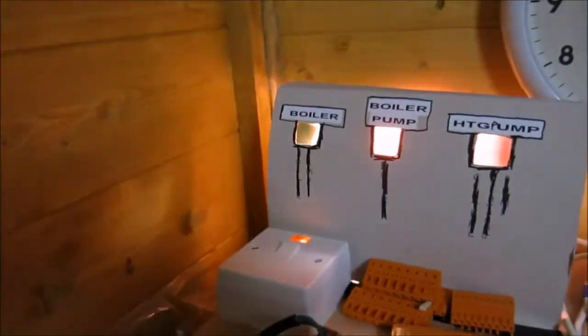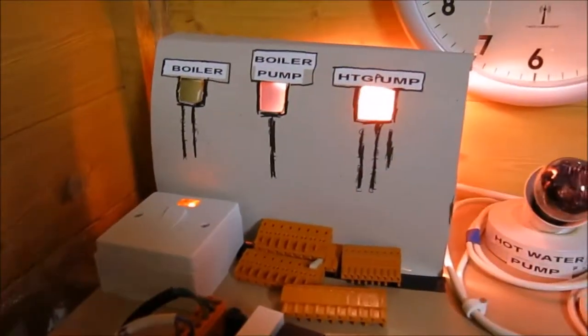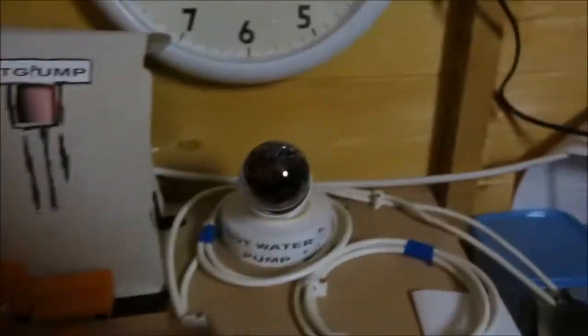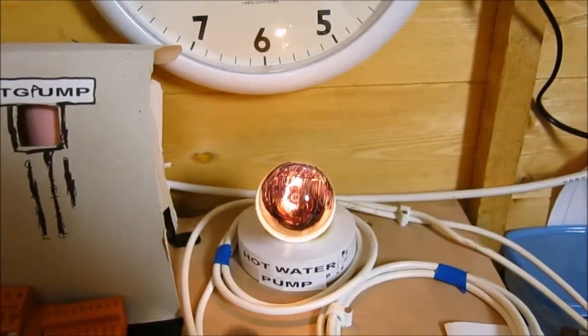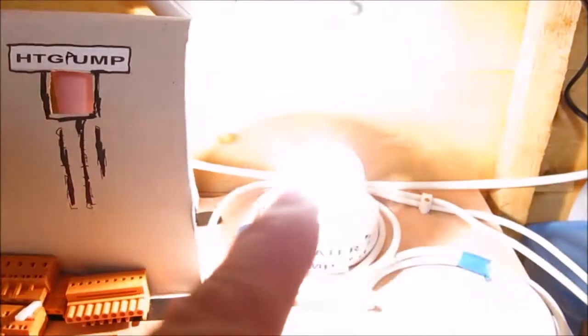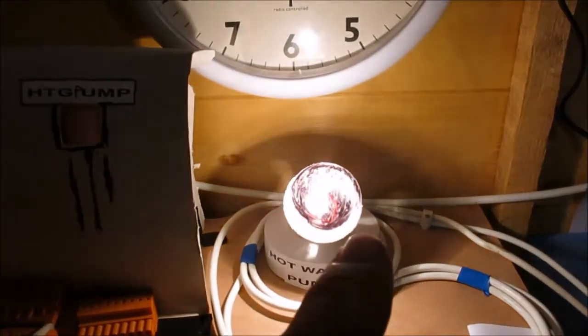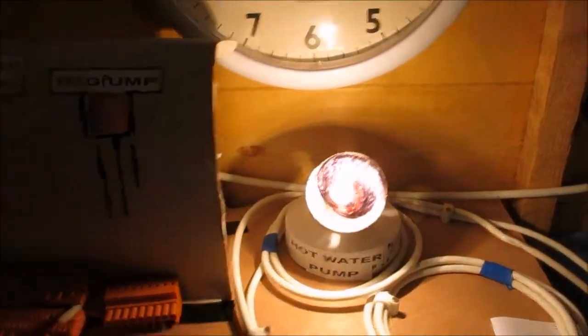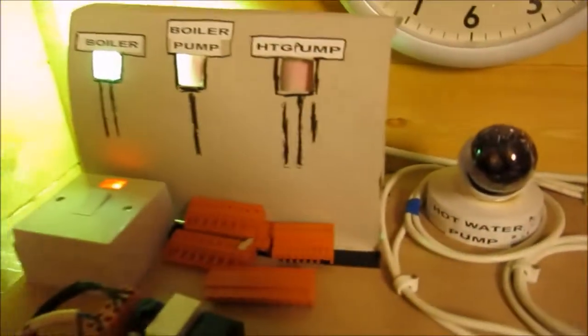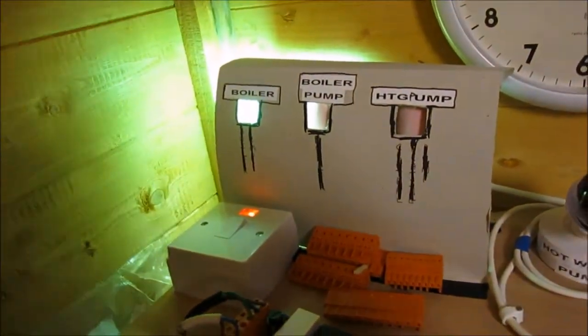So it'll run the boiler pump, the boiler, then the boiler pump, then the central heating pump. Then there's nothing on the next output. Then the direct hot water pump on low speed, then high speed, and then it'll flick back to, oh, that's because I've got that on, and then it'll flick back to the boiler output.